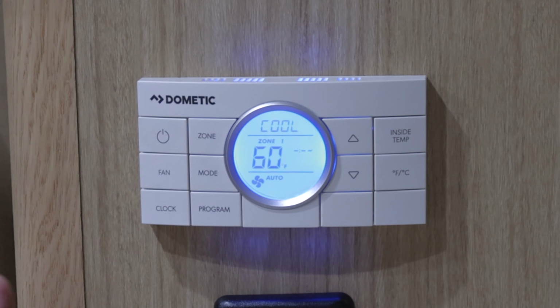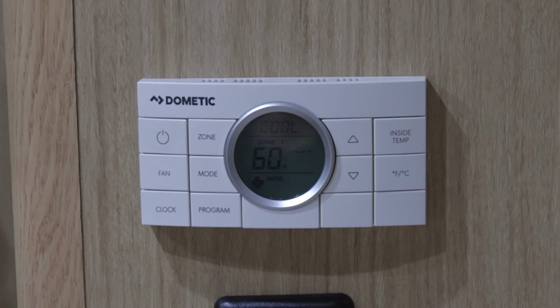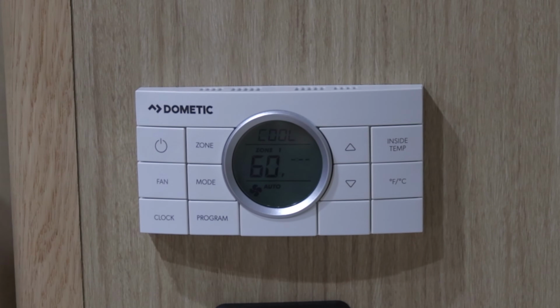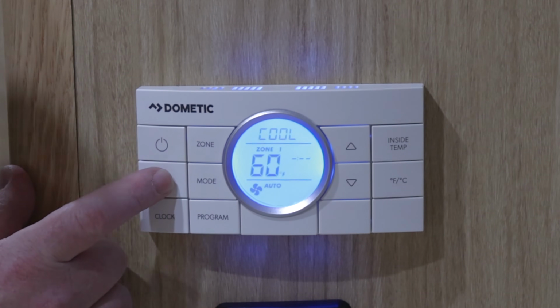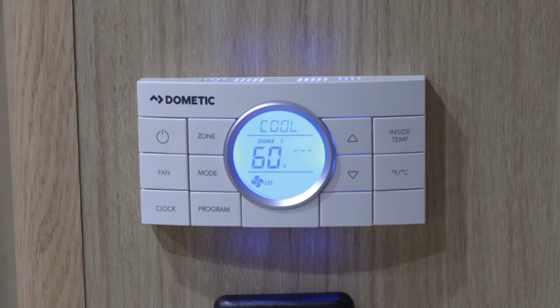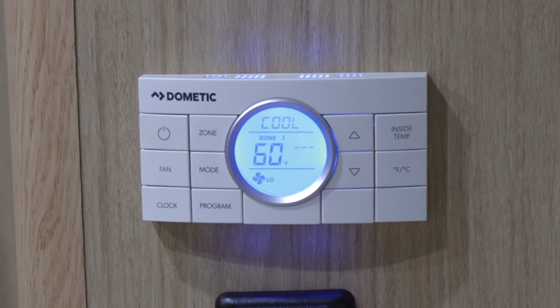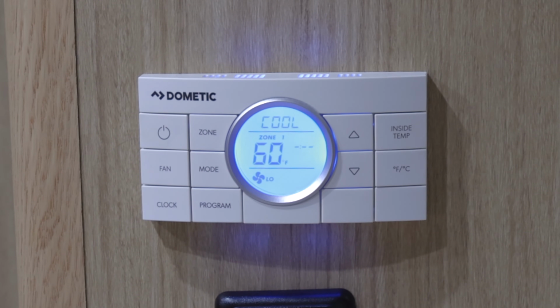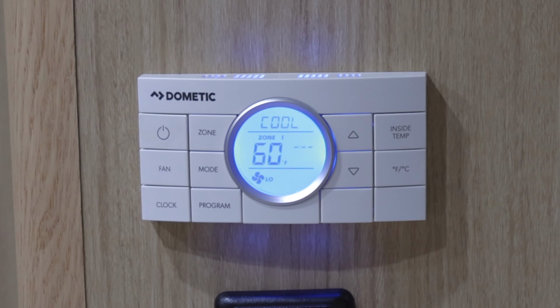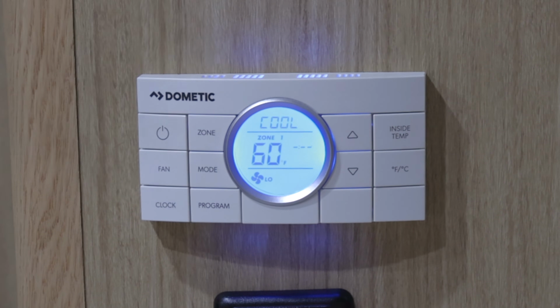Now, if you'll notice across the bottom, you'll see a fan symbol. It says auto. That's the fan speed. There are 3 speeds, and you're going to use the fan button to cycle through the options. It's going to go low, medium to high. Be patient with it. It's not going to react immediately, so we'll give it just a moment to catch up. There it goes. You'll see the fan drop down into its low speed. But make sure that when you're done, before you turn the unit off, you've returned the fan setting to auto, and that'll prevent the fan from automatically coming on when you turn the controller on.